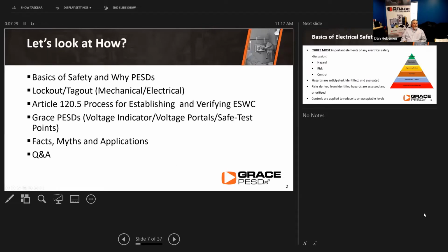Let's look at some of the basics of safety and why permanent electrical safety devices. As we talked about, one of the things that takes place every single day in a lot of facilities, and I would venture to say in most facilities, is they are doing lockout tagout procedures every day, both for mechanical reasons as well as for electrical. Now, Article 120.5 gives us the process for establishing and verifying an electrically safe work condition. What we do is we take devices that reduce that risk, and we present that into that process, and that's done through visual indication as well as voltage portals and also safe test points. And we'll talk a little bit about those different devices, and we'll also talk about some of the facts, myths, and applications as we go through, and then we plan on saving some time at the end for some questions and answers.